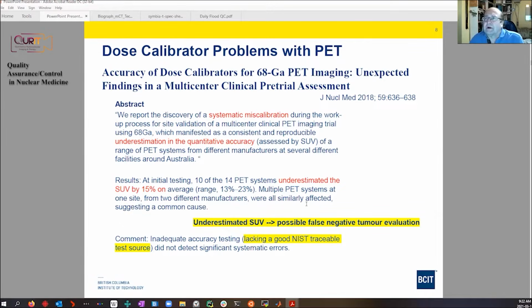So a question, how often do you perform tests? Some of the tests are performed daily. I'm not sure how often the accuracy tests are done, but I think the accuracy test can also be done daily. I don't remember how often they're doing it now in departments. So this should be picked up very quickly if there's a problem with the dose calibrator. But they were not able to get their accuracy.